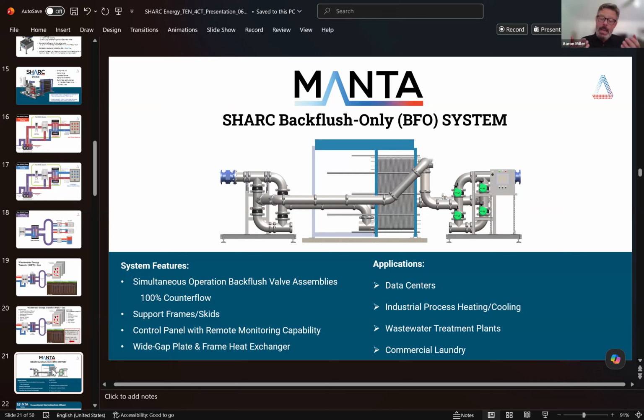So this is something that sprung from hotels and hospitals, but has really launched us into data centers, because those data centers have massive cooling loads. And here's an opportunity again, instead of wasting all that fresh water to cool them using evaporative cooling towers, use the Manta to harvest the energy from that data center and put it into a loop to then heat a nearby building, or put into the ground and save for heating, for seasonal usage. So again, we're not just about black water. We want you to think about hydronic energy, because moving energy between buildings using water, or essentially non-combustible sources like water plus glycol, is the most efficient way to do things.